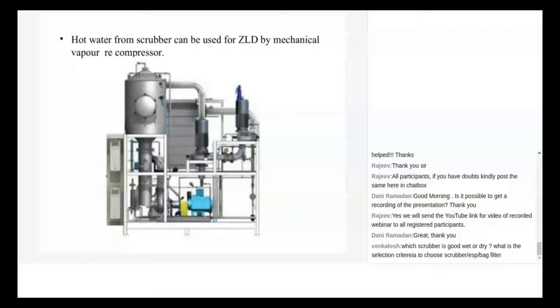But with mechanical vapor recompression, whatever vapor is produced - you can see in this figure - is recompressed by a blower, not a compressor of the air compressor kind. You have a head rise of only 5 meters, and then maybe at 70 degrees the vapors generated are compressed to maybe 74-75 degrees, and that is supplied as heating media in the jacket. So this is like a perpetual motion machine kind of thing, with some losses made up by mechanical power of electricity, which does the job of pressurizing the vapor generated so it has a higher temperature than the boiling point, going to 75 degrees. With that small delta T, of course, you need a very large heat transfer area.